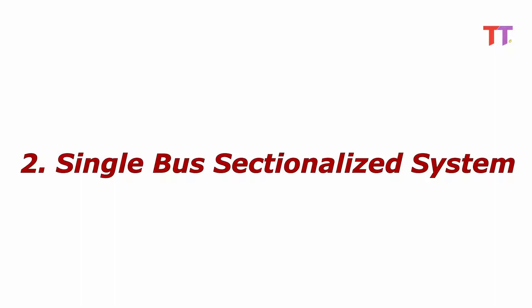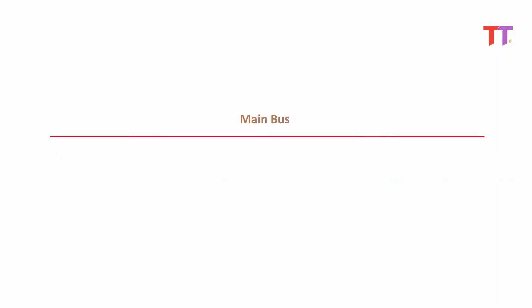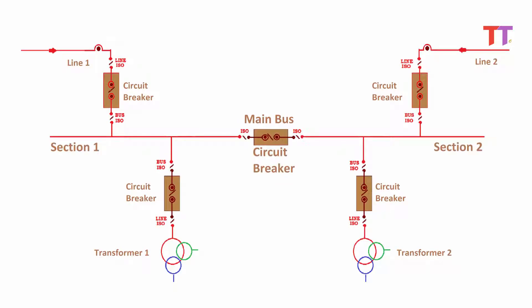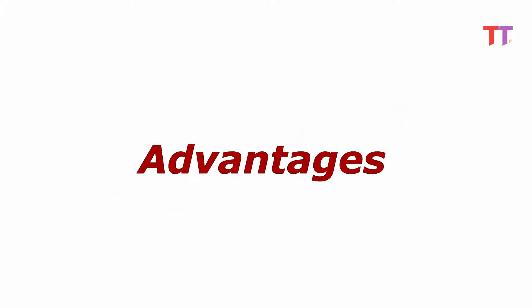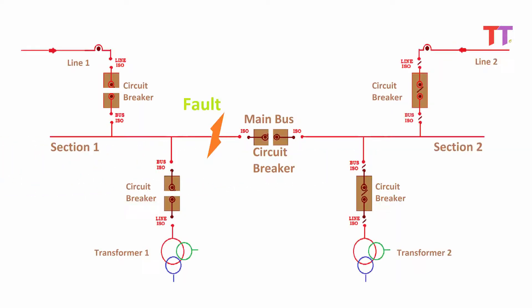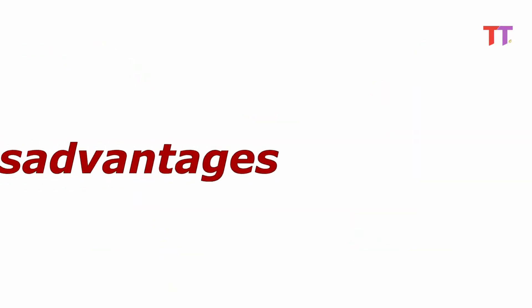2. Single bus sectionalized system. This is a single bus system with an additional circuit breaker and isolators, making two different sections of the bus, hence called the single bus sectionalized system. Advantages: since there are two sections separated by a circuit breaker, a fault on one section does not interrupt the other section — the circuit breaker isolates the faulty section from the healthy one. Also, maintenance of a bus section can be done individually without affecting the other section, hence power supply continuity is maintained.